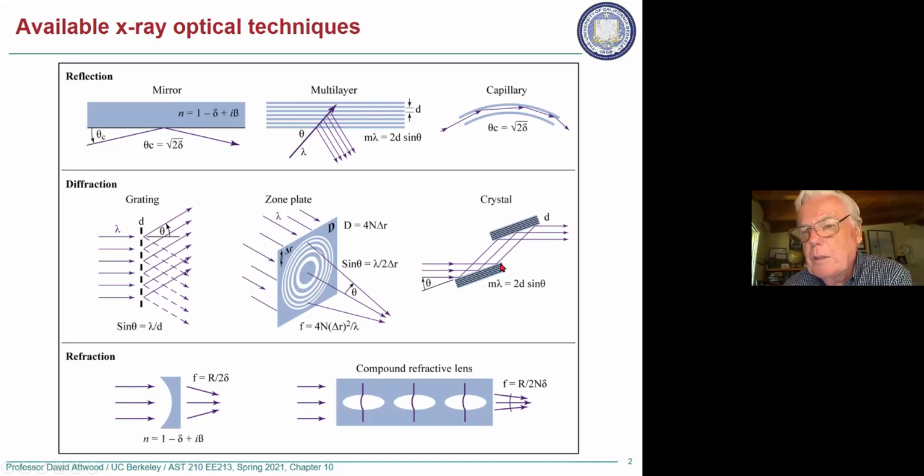So crystals are extremely valuable, mostly for hard X-rays. And again, at the Bragg angle, you can get 90 or even 95% reflection off one of these crystals of sufficiently narrow radiation, okay, and sufficiently well collimated. And this combination of 2 crystals is called a double crystal monochromator.